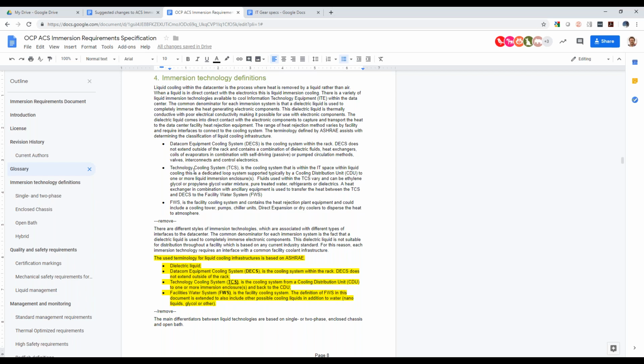Okay, so I'll continue reading here. Technology cooling system is the cooling system that is within the IT space, within liquid cooling, that is a dedicated loop system supported typically by a cooling distribution unit to one or more liquid immersion enclosures. Fluids used within the TCS vary and can be ethylene glycol or propylene glycol water mixes, pure treated water refrigerants, or dielectrics. Very good. Dielectric liquids in this case.